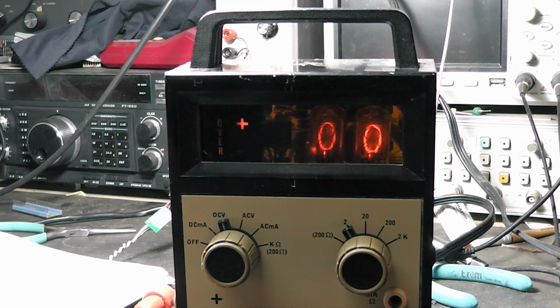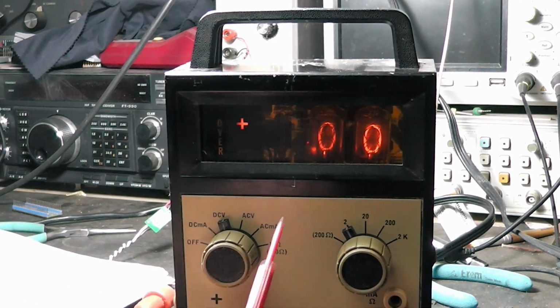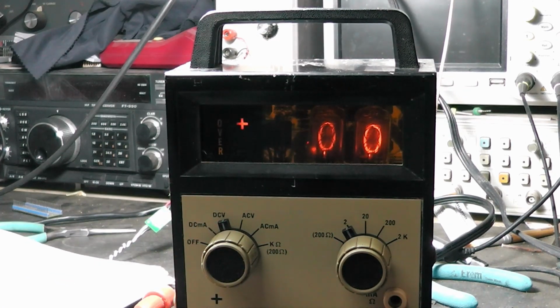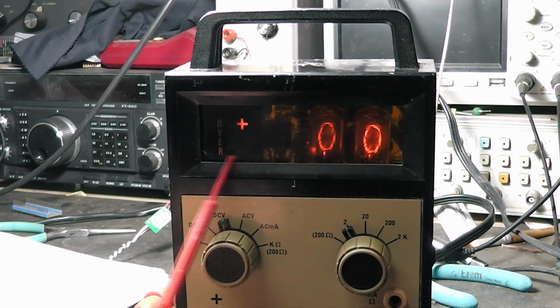It goes over using the alignment tool and all that stuff here in the book. With your function switch, it says to off, range switch to 2, polarity switch to plus, and plug it in and all that stuff, which I've already done. Turn the function switch to DC volt position and allow the unit to stabilize for at least 30 minutes. Note the plus polarity lamp and the 2 right hand digits displaying any number and the decimal point to the left of the digit should all be lit. No other lamp should be lit. That's what we got here.